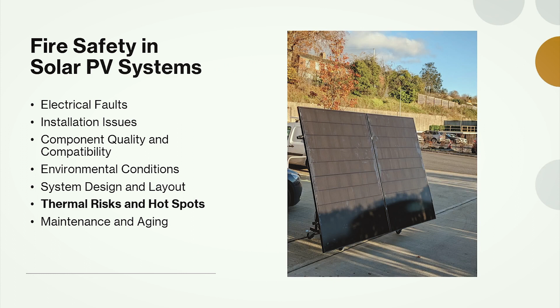Another thing in design would be maybe too dense clustering of solar panels together, not leaving escape routes and fire barrier issues. Thermal risks and hotspots. We get hotspots from solar panels if we have damage in modules, or if we have maybe a design failure where there's constant shade on some parts of the modules. And again, those things we try to fix by good design and good ventilation for the modules, and definitely maintenance. Keeping soiling away from the modules, and regular inspection and maintenance of the system. Thermal cameras are really good help where we can identify those hotspots.